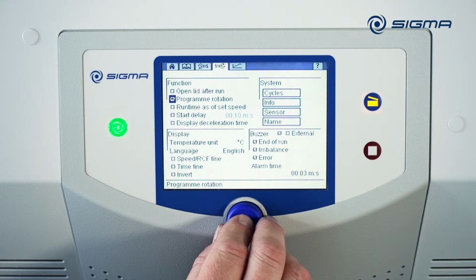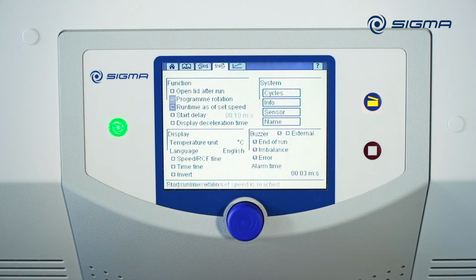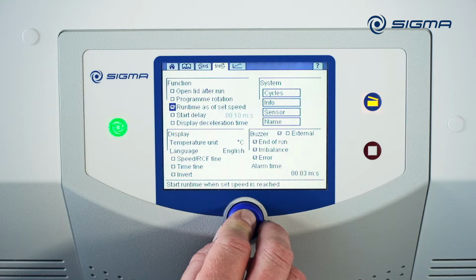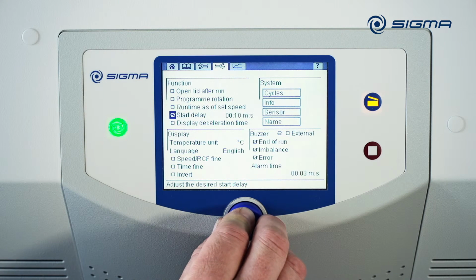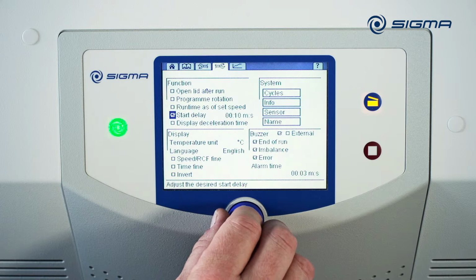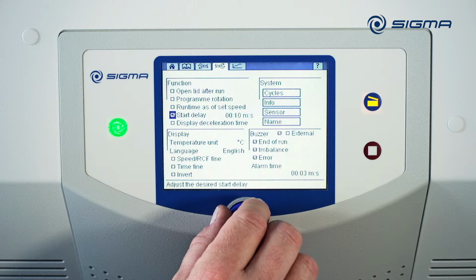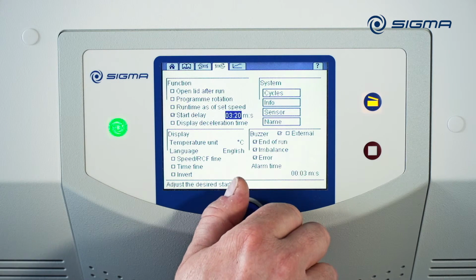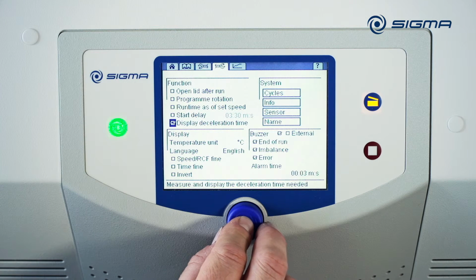If the Program Rotation option is enabled, the centrifuge processes all other saved programs after completing the first program and then goes back to the first program. If the Runtime as of set speed option is enabled, the centrifugation runtime does not start until the pre-selected speed is reached. If the Start Delay option is enabled, the centrifuge waits for the delay time to end before starting the actual centrifugation run. This time is configurable. If the Display Deceleration Time option is enabled, at the end of the runtime, the centrifuge displays the time it needed to decelerate to a stop from the set point speed.